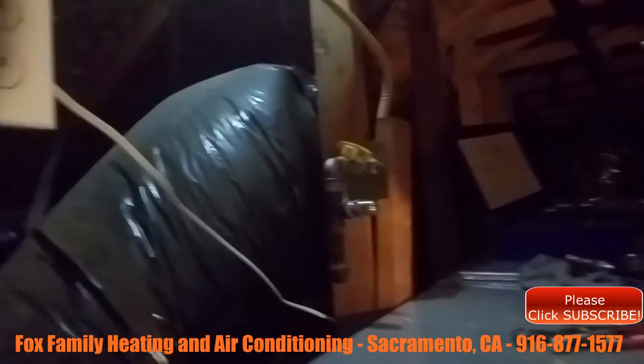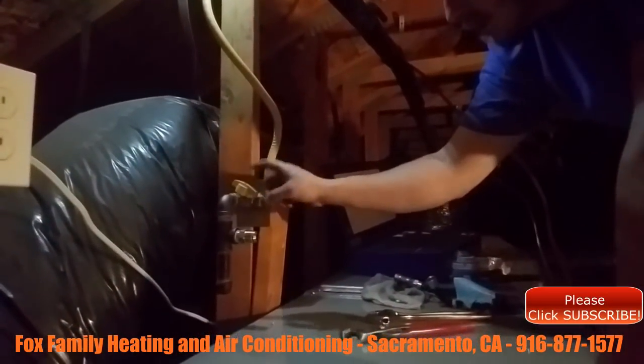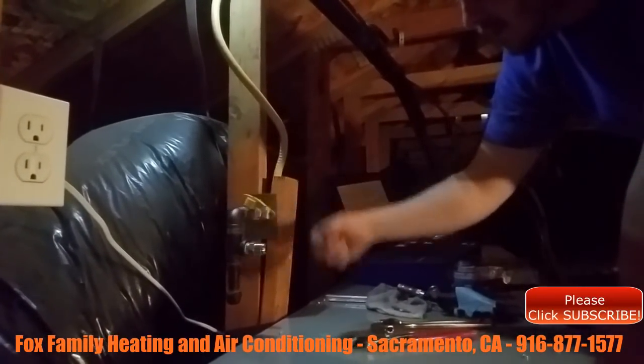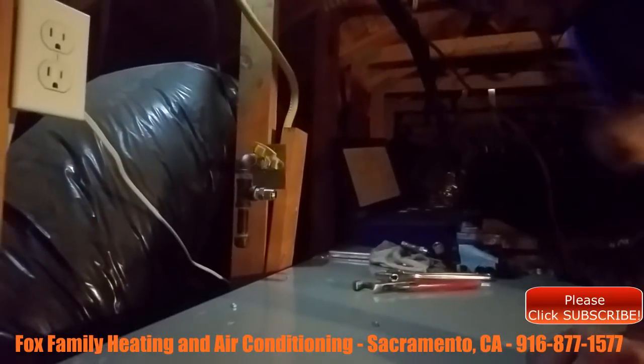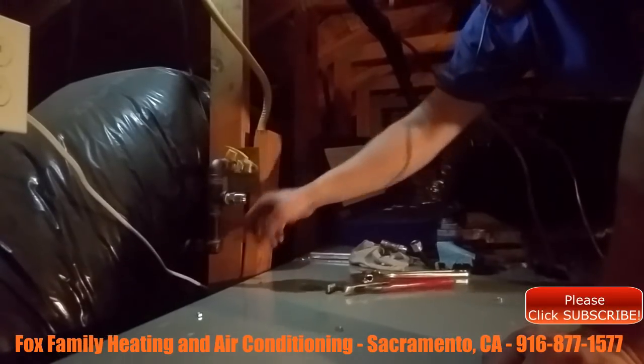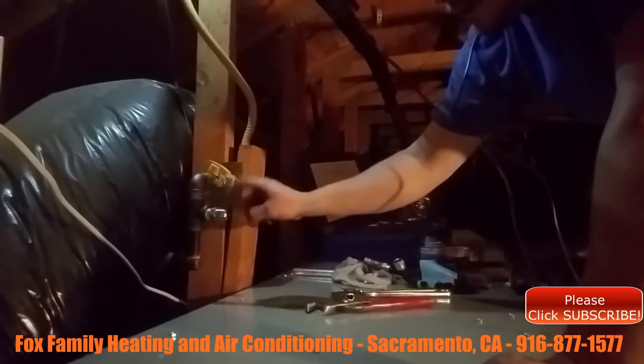Got his gas sediment trap up there going. We recently got dinged on that. Keith, you want to explain what we got dinged on? So we were putting the shutoff here, then running a straight piece, and then the sediment trap, and then having the top come off here. Sediment, if it throws straight into the T, it's not like it's magically going to go up into the piping, but this code inspector called us on it. He said, essentially, it has to be dumping straight down into the trap, and then the gas flex coming off the side. He didn't want the flex coming off the top, and then the shutoff being here. He wanted the flex coming off the side.